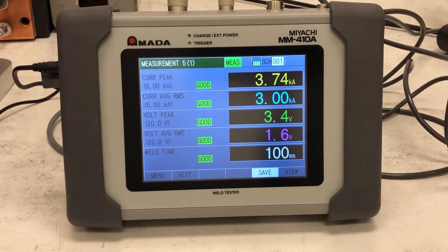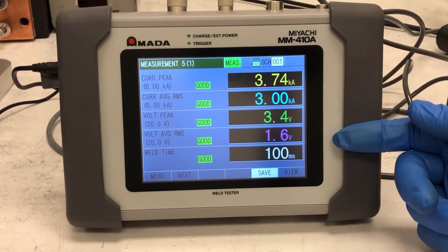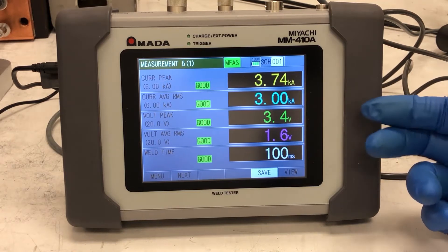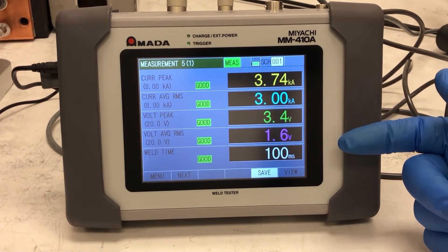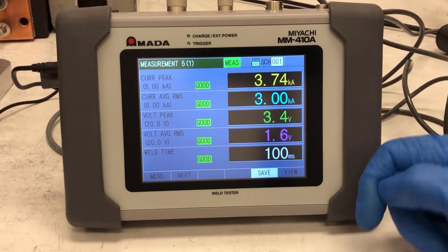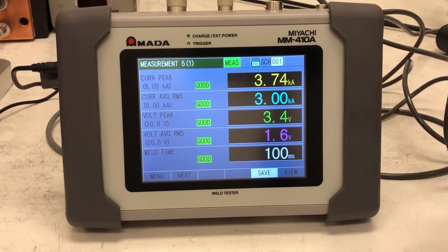We moved the voltage clips from across the electrodes back to the transformer to measure the health of the complete system — including the weld cables, the weld head bus, flexures, and across the part. Previously we had 0.9 volts RMS; now we have 1.6 volts. This tells us we picked up about 0.7 volts across that secondary, which is very good. If a secondary was declining, you'd see these voltages go up to 6, 7, or 8 volts, and you'd notice the current isn't reaching its target because the control is running out of voltage. The MM410 is a very effective way to troubleshoot system health back at the transformer.